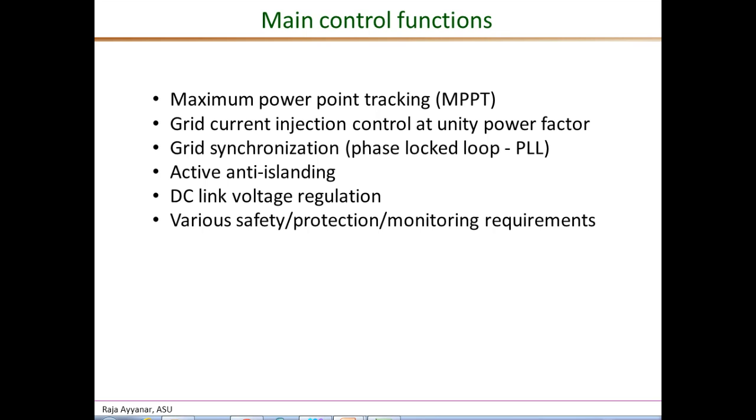It is not trivial to detect an island, especially when the local load matches exactly with the PV generation. We need to have some kind of an active positive feedback based method in order to detect an island. That is the function of this anti-islanding control loop. Internally, we have this DC link voltage which determines the voltage rating of the various power semiconductor devices, and they need to be quite precisely regulated. That is one of the main control loops.